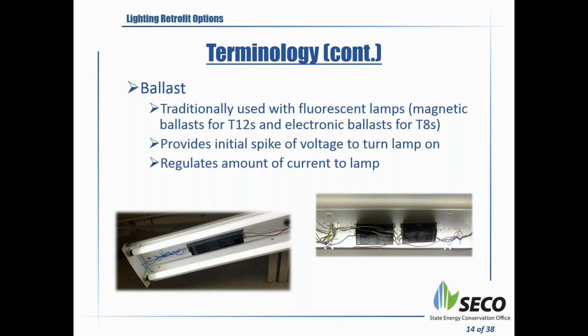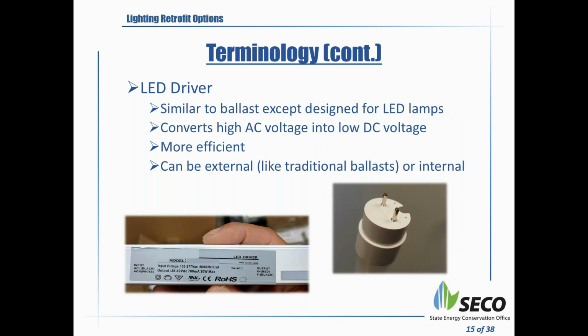So that's something that everyone knows, but I thought I'd just mention it, and there's a reason for mentioning it, because when you go to LED lighting systems, you will hear the term driver. The LED driver has almost the same function as the ballast in fluorescent lamps. So you still need some sort of a driver in LED systems. It is similar to a ballast, except designed for LED lamps; it converts high AC voltage, which is alternating current, into low DC voltage. It is more efficient.